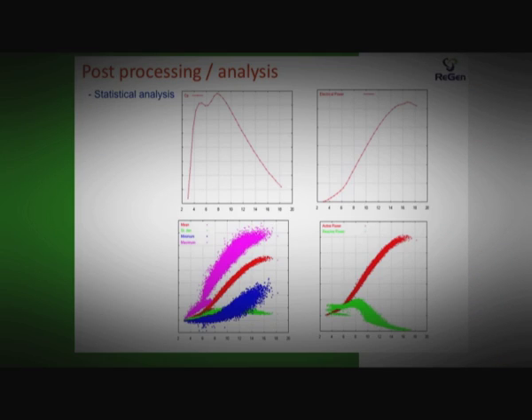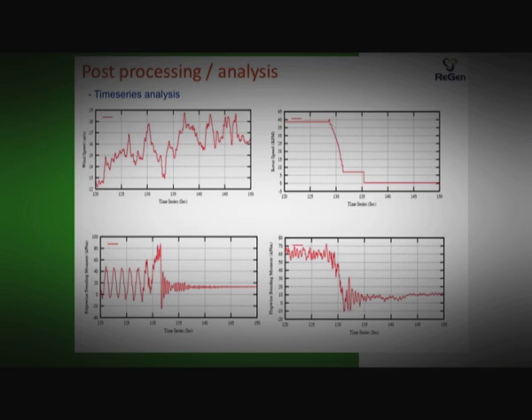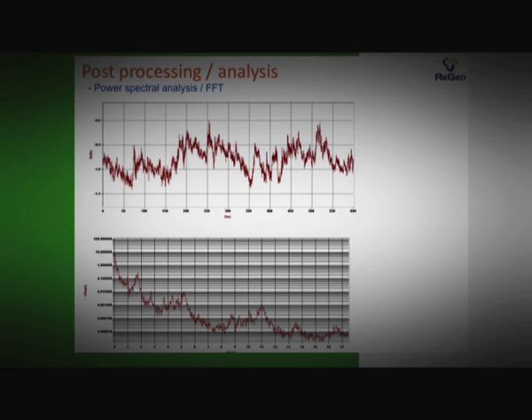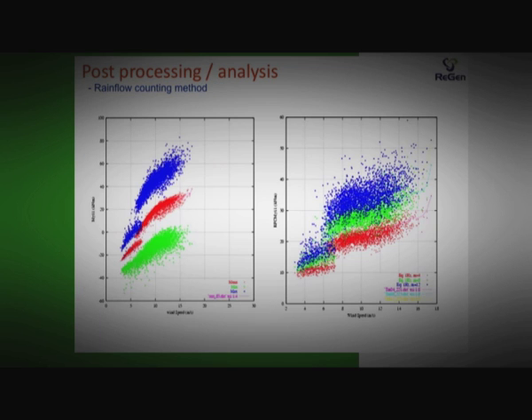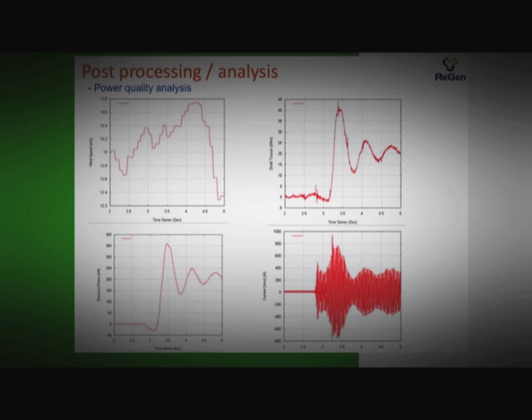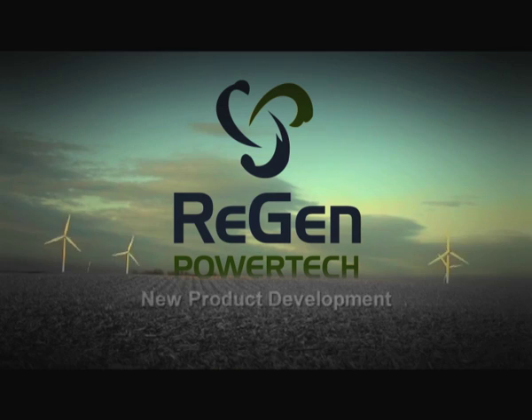During post-processing, we do several mathematical treatments, starting from statistical analysis and time series analysis, which involves power spectral density analysis and fast Fourier transformations. We also do rainflow counting for calculating the fatigue loads to determine the lifetime damage of critical components like the tower, shaft and blades. And we also do power quality analysis, where we find out the flicker coefficients and the harmonic distortion in the power delivered by the wind turbine.